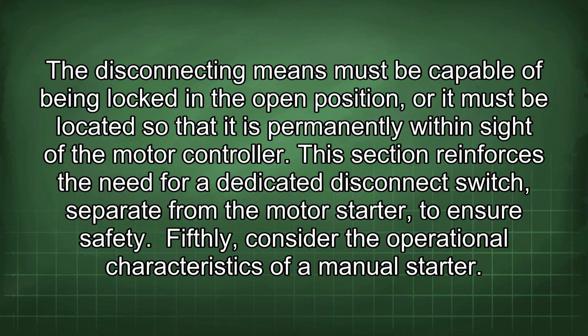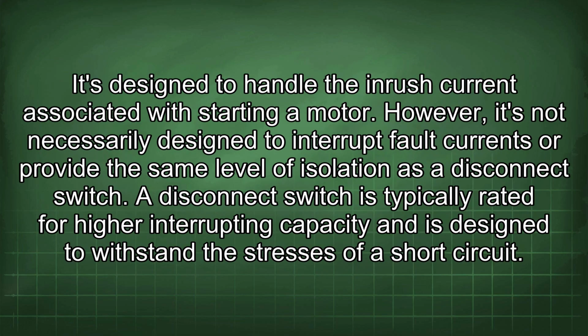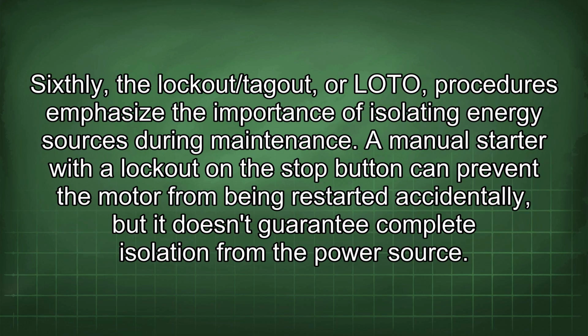Fifthly, consider the operational characteristics of a manual starter. It's designed to handle the inrush current associated with starting a motor. However, it's not necessarily designed to interrupt fault currents or provide the same level of isolation as a disconnect switch. A disconnect switch is typically rated for higher interrupting capacity and is designed to withstand the stresses of a short circuit.